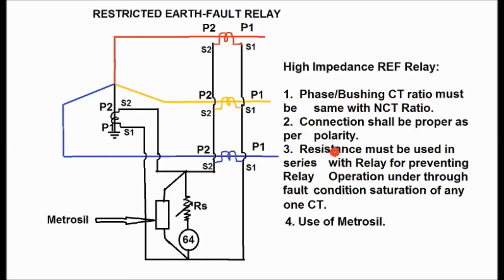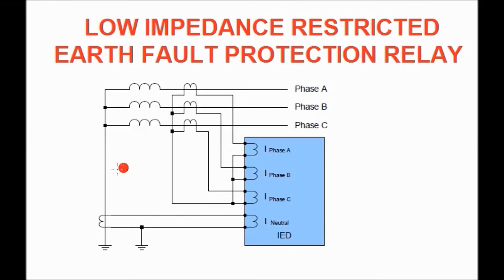The condition for using the high impedance type is that all the phase CT ratios must be the same as the neutral CT ratio. If the phase CT or bushing CT ratio is not the same as the neutral CT ratio, we cannot use the high impedance type restricted earth fault relay — in that case we must use the low impedance type restricted earth fault relay.